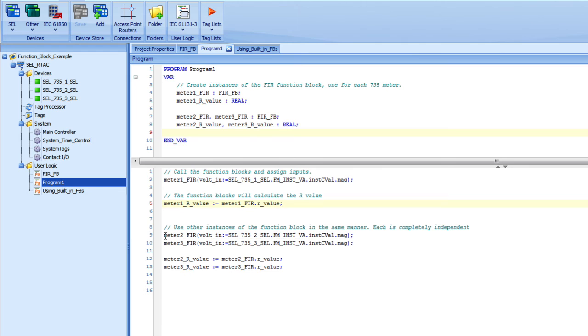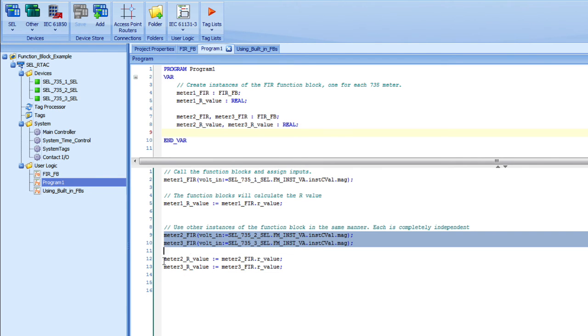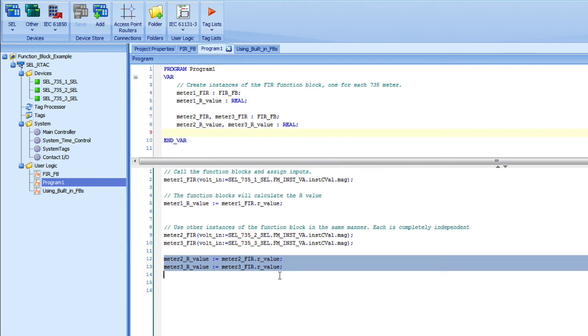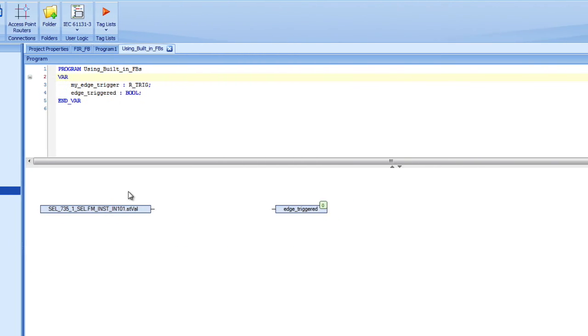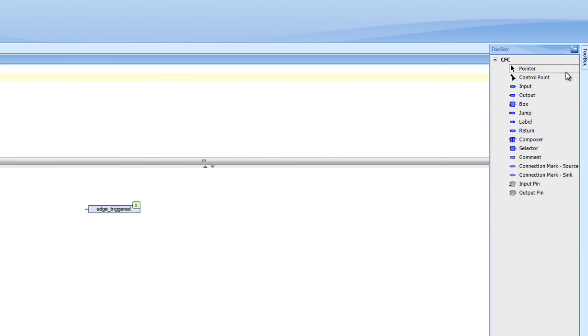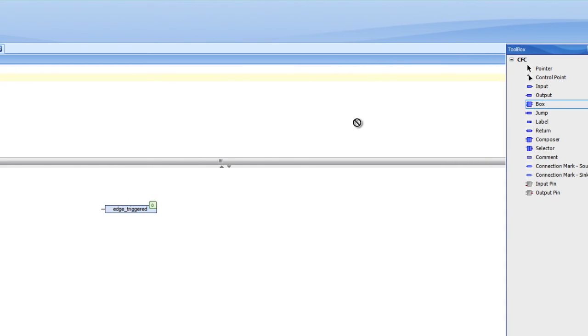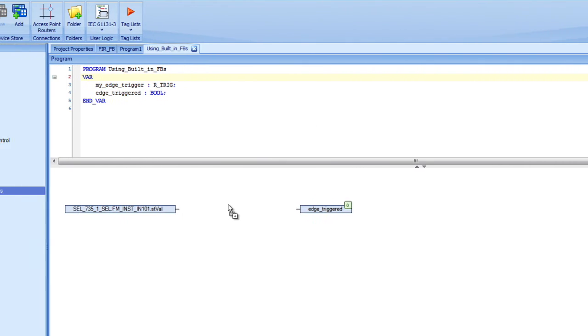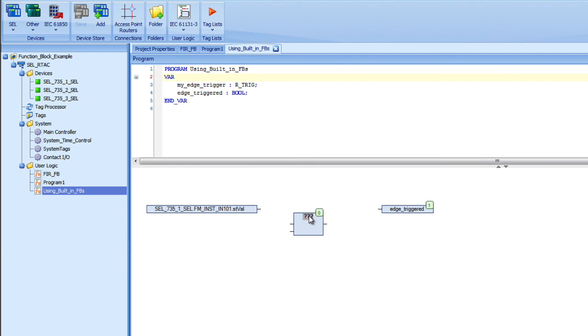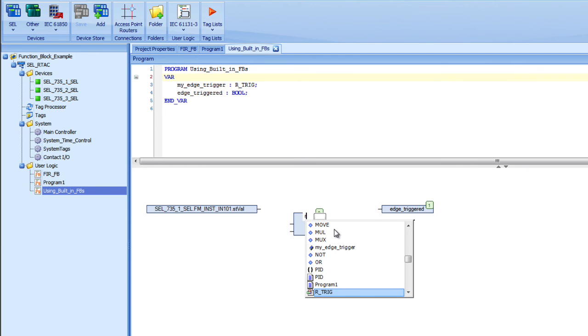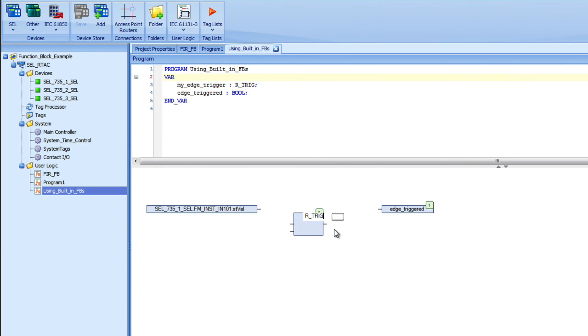We can see that we can do that multiple times with any of these other instances. There are also built-in function blocks into 61131 that we can use. Here I have a program that is a continuous function chart. As we discussed previously in another video, I can drag a box over there. I have a box here and I can just start typing R_trig or whatever the function block that I want to use is. It will show up here in the input assistant. I select it.